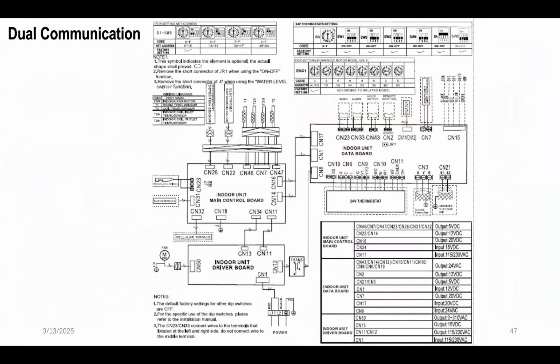All right, here's the wiring diagram out of the box, or in the manual. Here's your 24-volt thermostat connections. CN7 right here, that's your HA and HB. CN21 here is your S1, S2 to your outdoor unit. You have your interconnecting cables. All of your sensors report back to the main board. The main board then communicates those to the display board. The main board sends out the signal here on CN34 for your blower control.